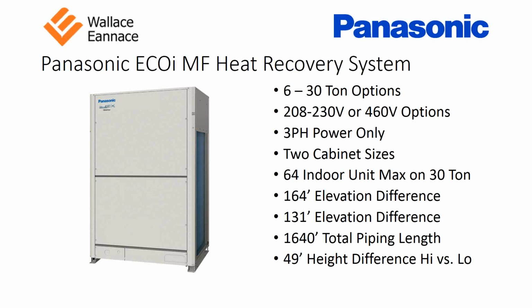So a good application for a system like this would be a lot of offices in an office building. You have some people in an office who are hot, they want to have AC on, and then you have other workers in other offices who are cold who want to put the heat on. With this system, you can achieve that, all piped back to one condensing unit. So all the other manufacturers can do that, but this is the way of the future when it comes to heating and cooling spaces.